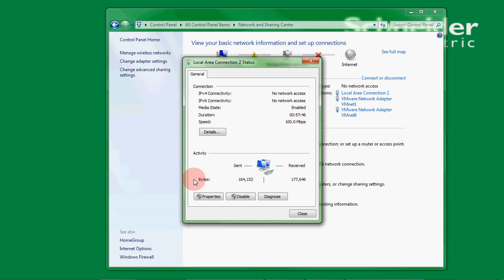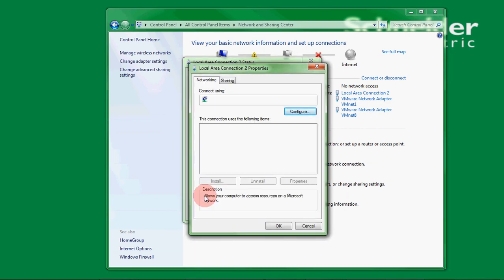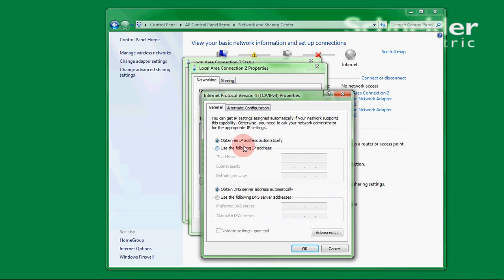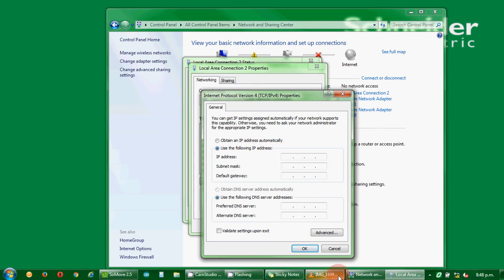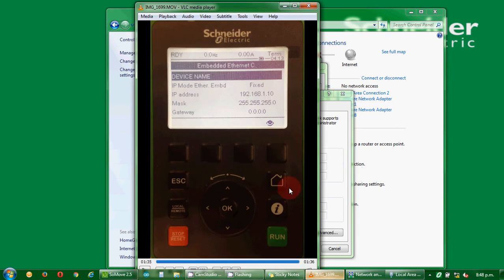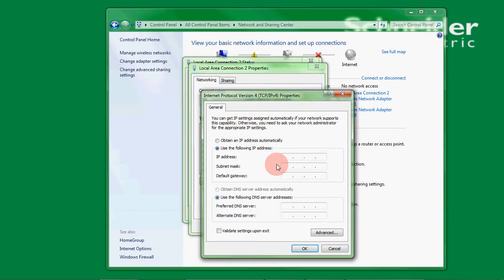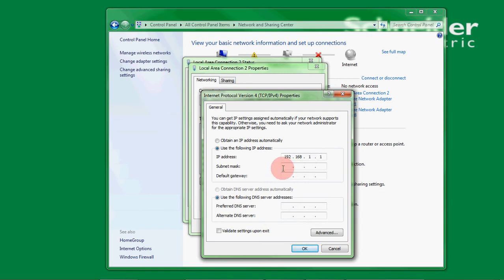Click on it and then select properties, and then we need to select internet protocol version 4. Double click on that and we give our PC a static IP address. Now it needs to be similar to the drive except we cannot give it the same number in the last field. So we will give our PC an address of 192.168.1.1 and again the subnet mask needs to be 255.255.255.0.